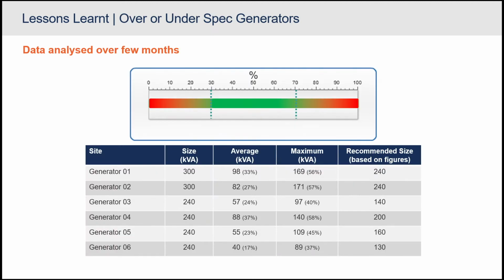Okay, next one: talking about over and under spec of generators. This can be a topic on its own, but the rule of thumb is you want to spec your generator correctly. If it runs, you're not supposed to let it run at less than 30% of its capacity.